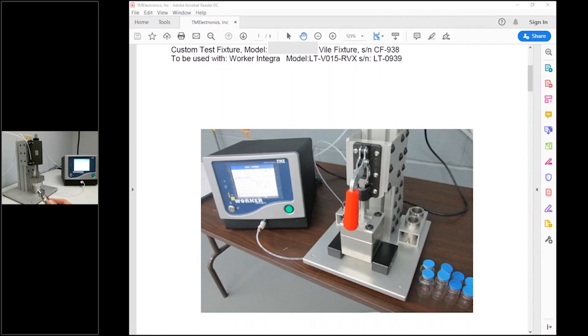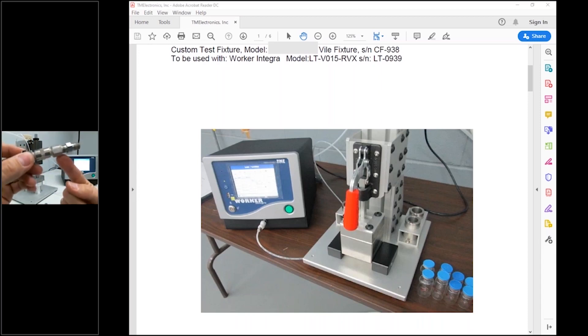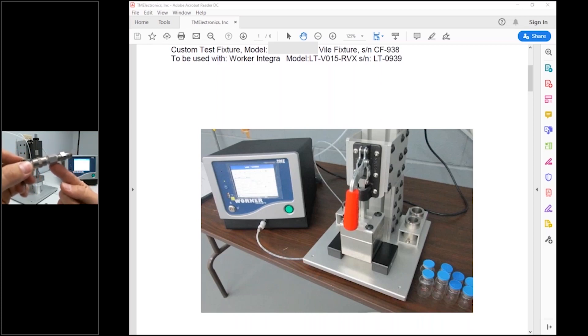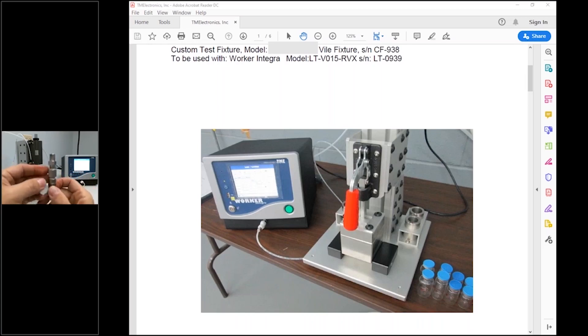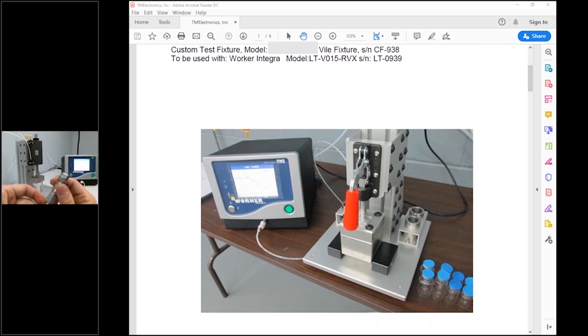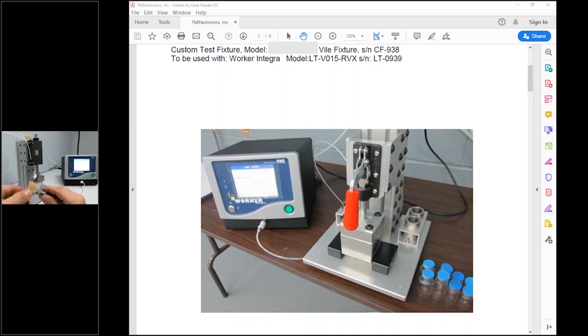We ship with what we call an LAO, or leak orifice. The leak orifice has a quick-connect on one end, and then there's a very tiny micro-orifice — usually two, three, four, or five micrometers. Five microns is usually what you want to detect for your typical leak test leak rate. The other end is usually either a filter or, in this case, it's open, which is fine for positive pressure testing. This would typically get installed with a T-adapter if you want to do inline fault detection, so you can install a fault into your system and verify that you can measure it.